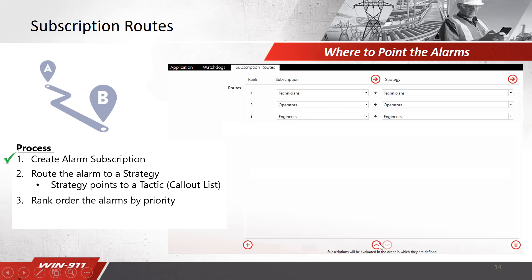You have the ability to move these items up and down to rank-order your subscription filters. Typically you put your highest priority or most critical alarms at the top. In a scenario where your alarm is not caught by a subscription — maybe incorrect case sensitivity, since these items are case sensitive, or maybe you mistyped something or didn't filter on the correct criteria — the alarm would filter through all of these and not go anywhere.